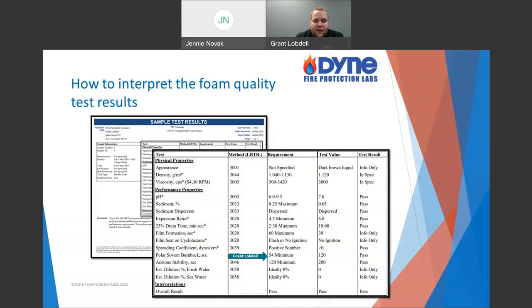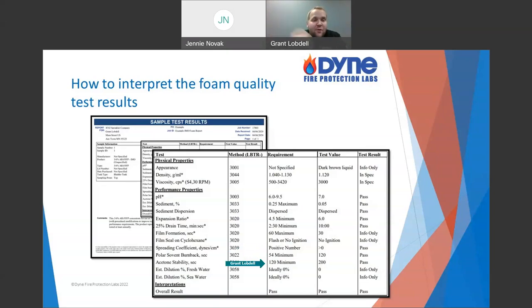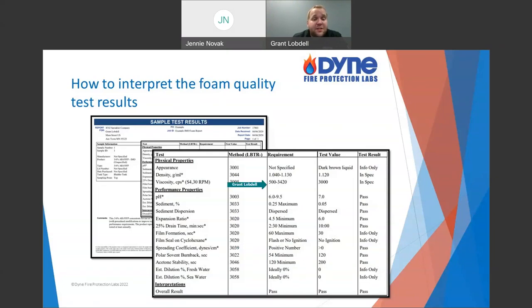Burn back and acetone stability are alcohol-resistant tests required only for IMO — you won't see them on NFPA unless requested. Why would something fail those tests? Age, storage conditions, dilution — or it's not really alcohol-resistant, or it's lost some of its alcohol-resistant performance because the polymer is low. If it failed one of these alcohol-resistant tests, the first thing I'd do is look at viscosity to see if it still has all the polymer it's supposed to.